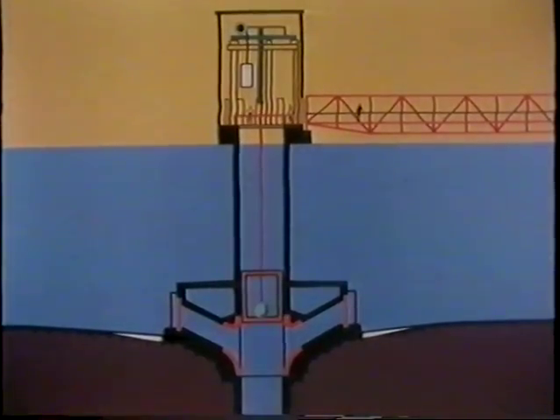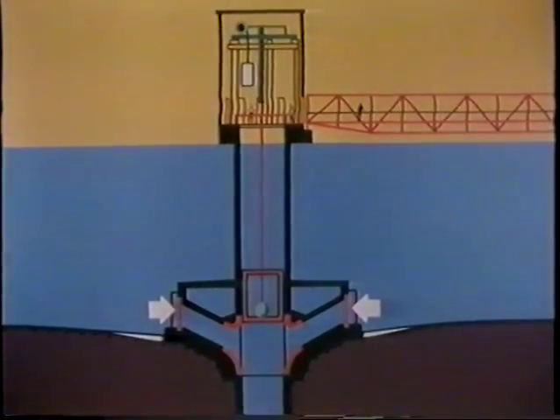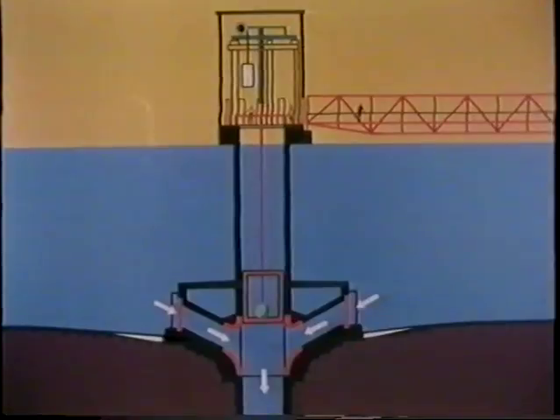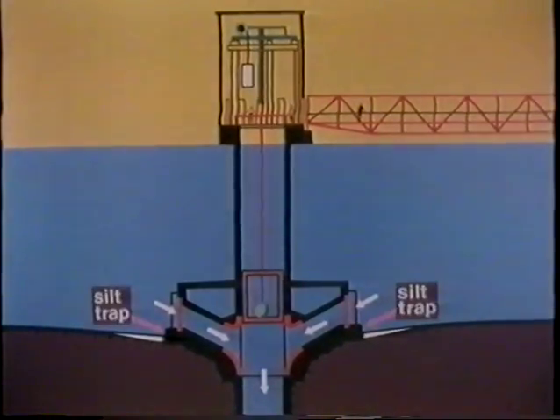The intake channels are protected by 40mm screens to prevent the entry of large foreign objects which might damage the pressure conduit, not to mention the valves and turbines down below. A silt trap collects small stones, etc.